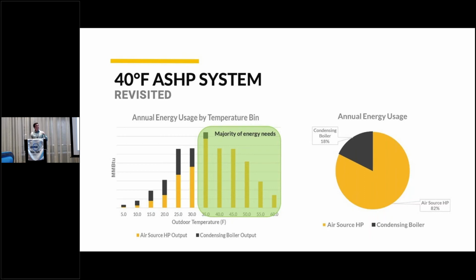Then, once the temperature starts to drop, we're going to fire up our heat pump, because that's where we'll capitalize on the electrified heating. Once that's maxed out, if we're in these lower temperatures, only then will we fire up our condensing boiler. So it was really incredible to see that this system, while not fully electrifying the building, is having an 82% reduction in fossil fuel usage.